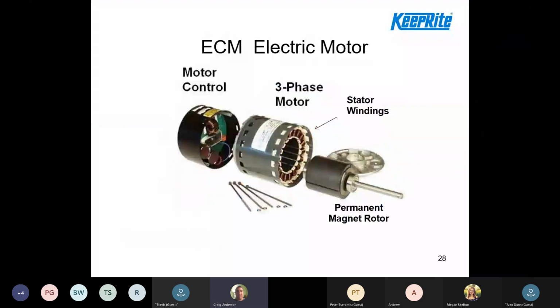For an idea of what your ECM motor looks like, you usually have the end bell on it, which is the motor control. Then we have the 3-phase motor. So we're changing voltage from single phase to 3-phase going into our motor. Stator windings and a magnet inside.